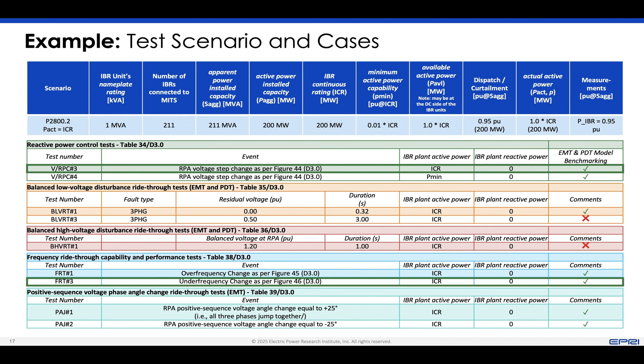It has a fairly aggressive control, and we see that both models, the PDT model and the PSCAD model, are in fairly good match with each other, and they both adjust their reactive power within about a second of the RPA voltage step change. Now, when we go to a weaker grid condition of 2.5, what we see is that the plant response is much faster with those same control parameters. So the question comes up, okay, is this kind of high voltage, when the voltage changes, still acceptable from a conformity viewpoint?